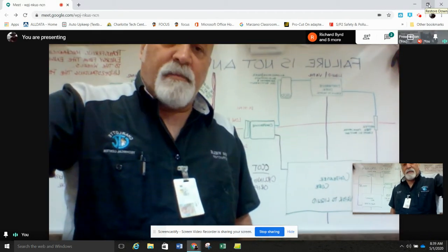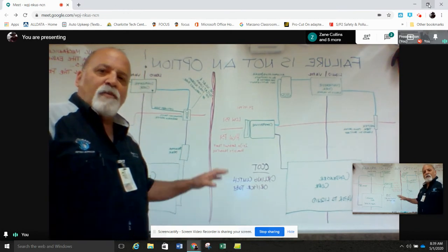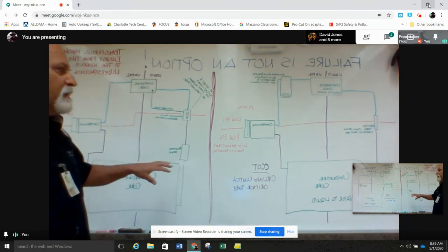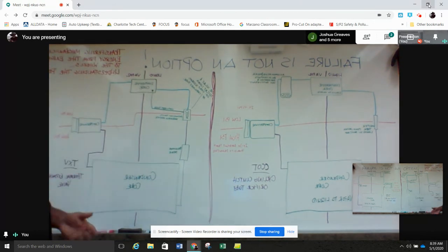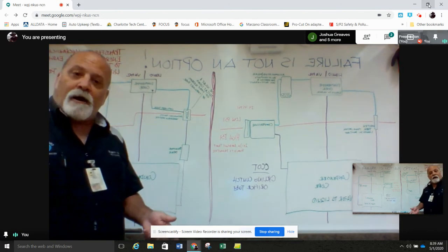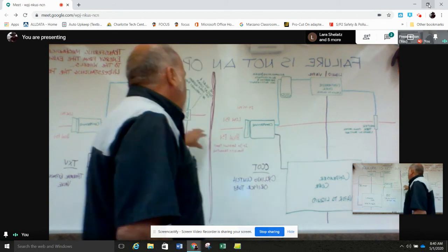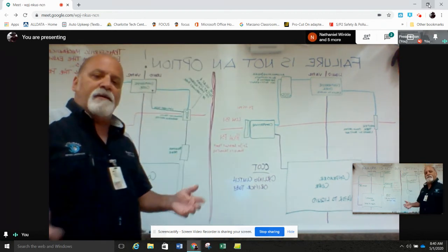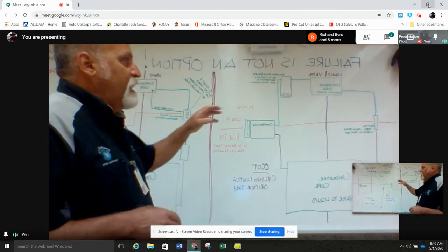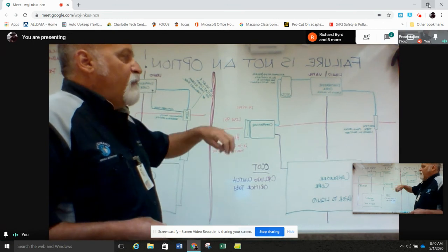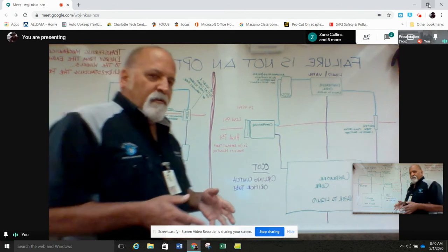What we're talking about is the principles and the actual operation of an air conditioning system. I have two drawings on the board that look almost identical, and for all practical purposes they are. They're just two different types of systems used for air conditioning — they operate on the same principles. One has a variable orifice and the other has a fixed orifice for vaporizing the refrigerant.